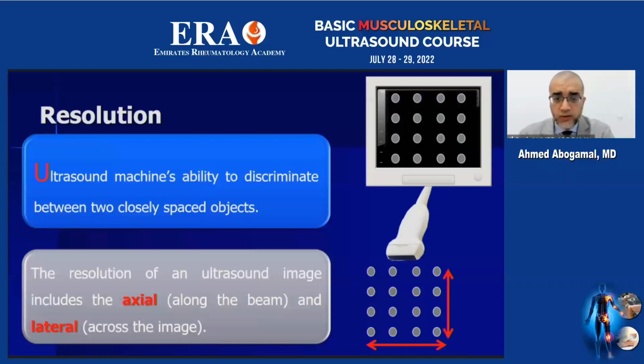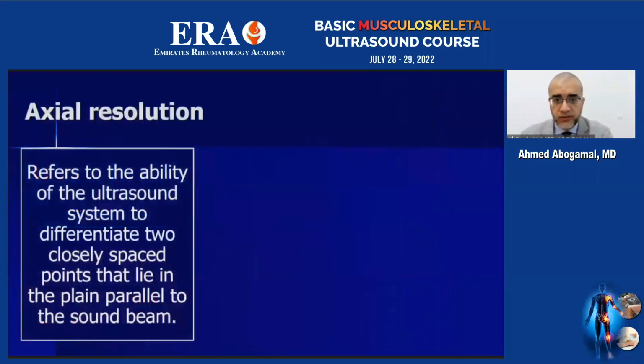For the resolution of the ultrasound image, we have two types based on the direction of the ultrasound wave and the relation between the two adjacent points. Either it is along the beam, which we call axial resolution, or across the beam, which we call lateral resolution. Each of them is an important determinant of the quality of the image.